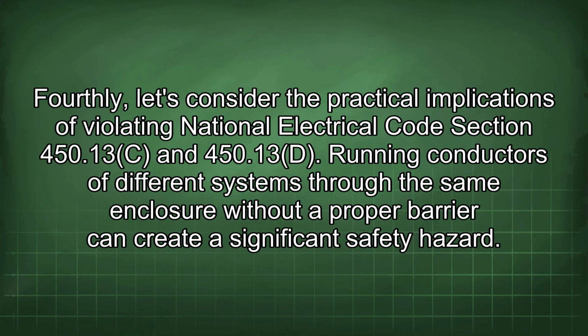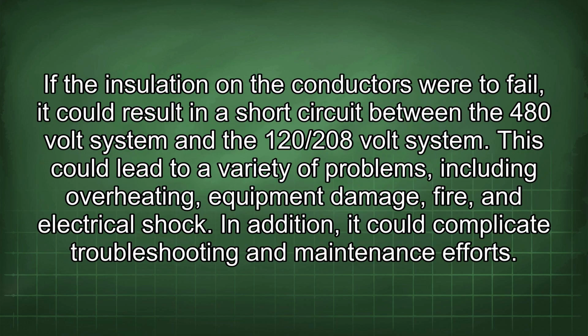Fourthly, let's consider the practical implications of violating National Electrical Code Section 450.13c and 450.13d. Running conductors of different systems through the same enclosure without a proper barrier can create a significant safety hazard. If the insulation on the conductors were to fail, it could result in a short circuit between the 480-volt system and the 120/208-volt system. This could lead to a variety of problems, including overheating, equipment damage, fire, and electrical shock. In addition, it could complicate troubleshooting and maintenance efforts.